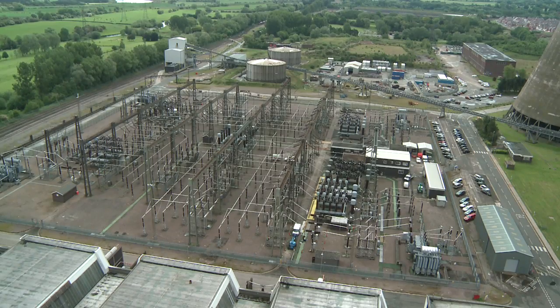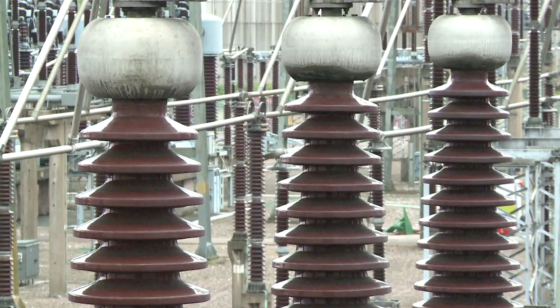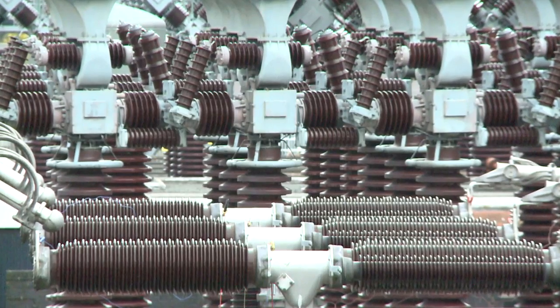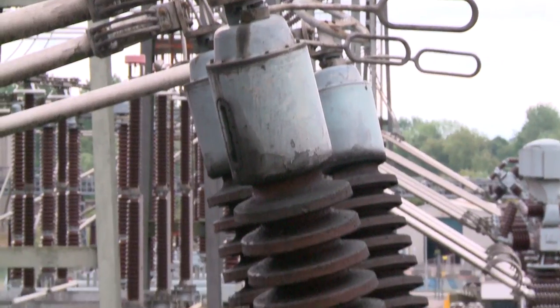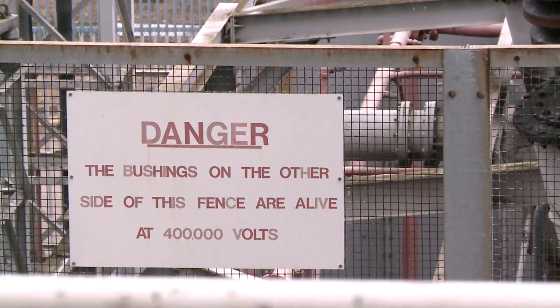I can think of no more difficult combination of materials than high voltage electricity, water to cool it, and hydrogen to keep the rotor cool. You have a problem of containment of the water and the hydrogen. If hydrogen escapes, you could have a serious explosion. If water contacts the copper at high voltage, you could have an even bigger explosion with electricity. The electricity is made at 11,000 volts, but to ship it about the country on the high voltage grid, the higher the voltage the cheaper it is to move — so in fact, we transform the electricity up to 400,000 volts and ship it about the country.